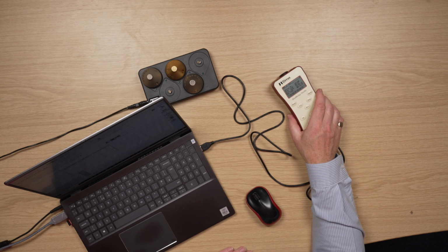It's also very good practice to actually put down the serial number of the device that did the calibration as well, because not only do your dosimeters need to be calibrated on a regular basis, but also your calibrating device needs to be calibrated on a regular basis, and in this case it's the reader unit.